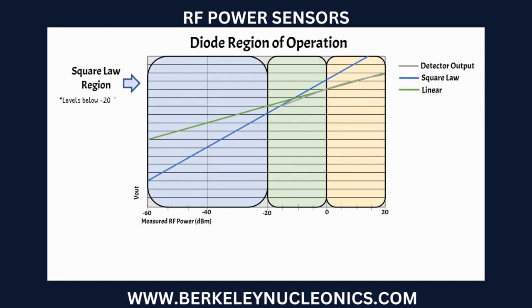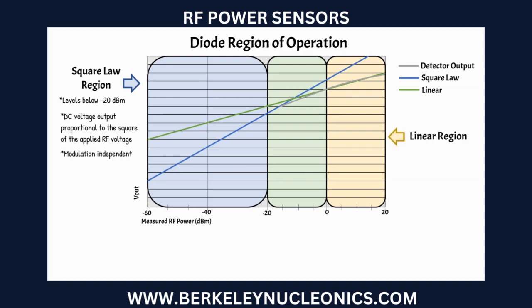The diode region of operation is typically separated into three sections. The square law region occurs at levels below about -20 dBm, where the diodes produce a DC voltage output that is closely proportional to the square of the applied RF voltage. This region is also modulation independent.